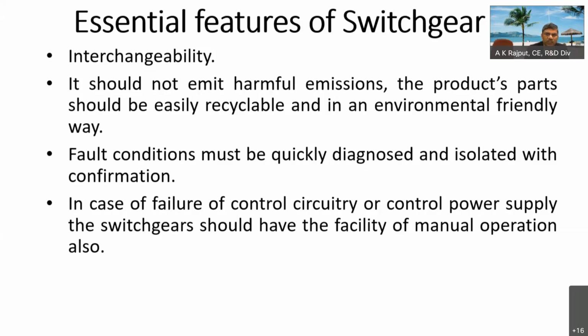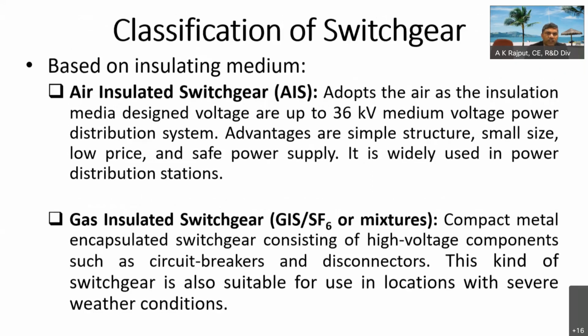Fault conditions must be quickly diagnosed and isolated with confirmation. It should also give an indication that the fault has been cleared, and the signal should go to the control room in an affirmative and confirmative way. In case of failure of the control circuitry or control power supply, the switchgear should have the facility of manual operation also. Sometimes the control power supply from the batteries fails or the cable gets cut. So there should be a provision for manual operation of the circuit breakers, from local or from remote, both.